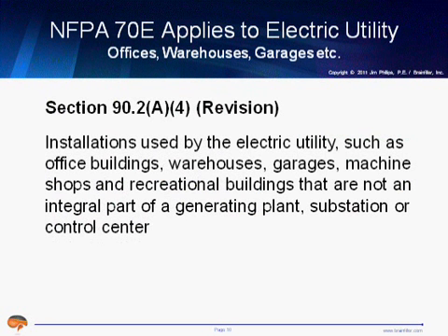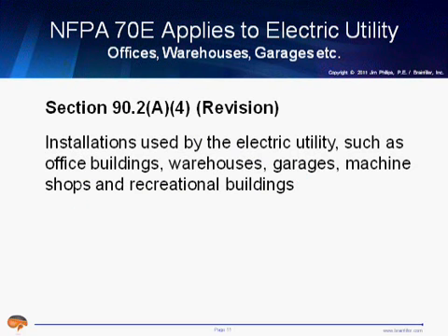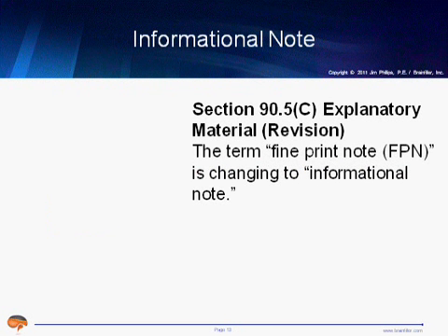The applicability is with electric utilities if they have office buildings, warehouses, garages, machine shops, recreational buildings that previously it said that are not an integral part of a generating station or substation or control center. Well, that's being deleted. And now it's going to be just left with if you have office buildings, warehouses, garages that are part of an electric utility, this applies to them as well. That seemingly exemption wording is being eliminated. Informational notes, this is being changed to be consistent with other NFPA documents.